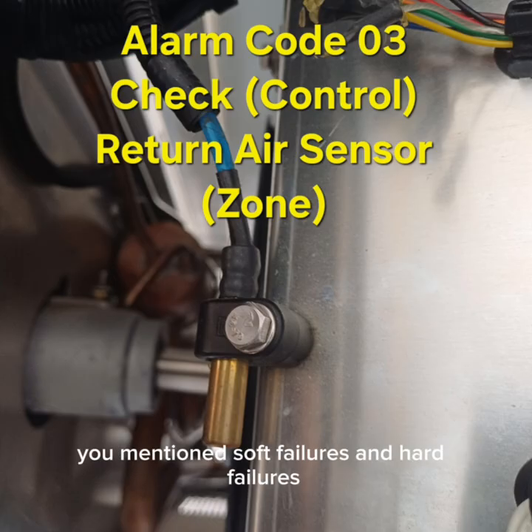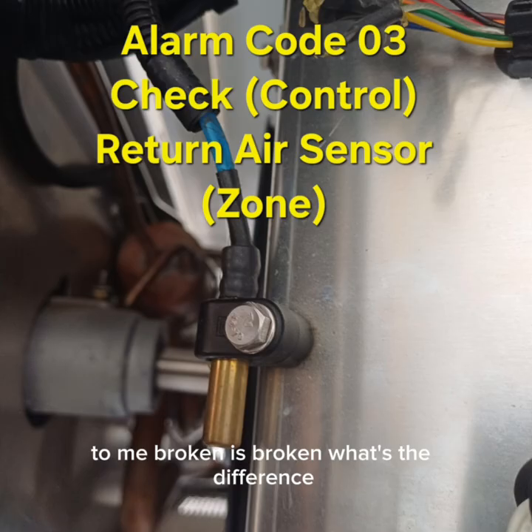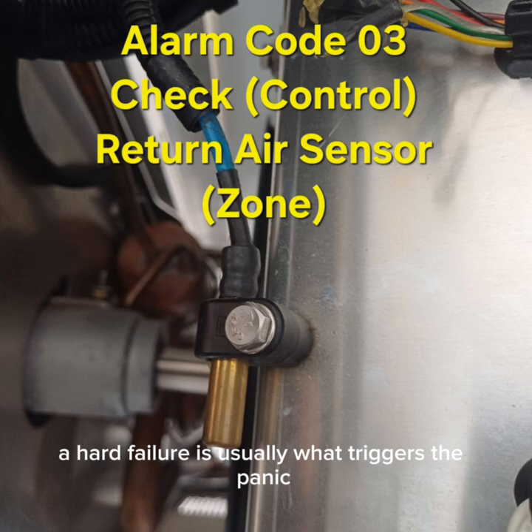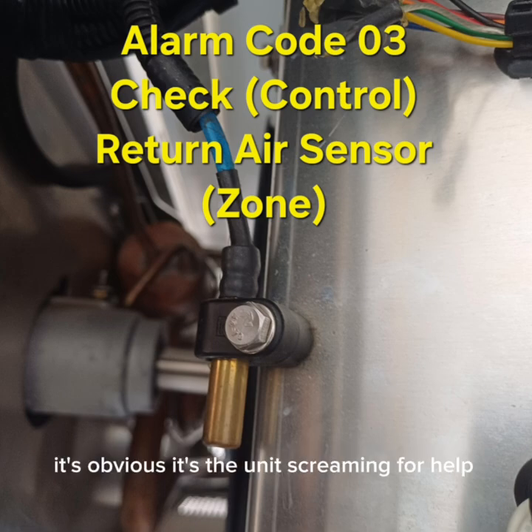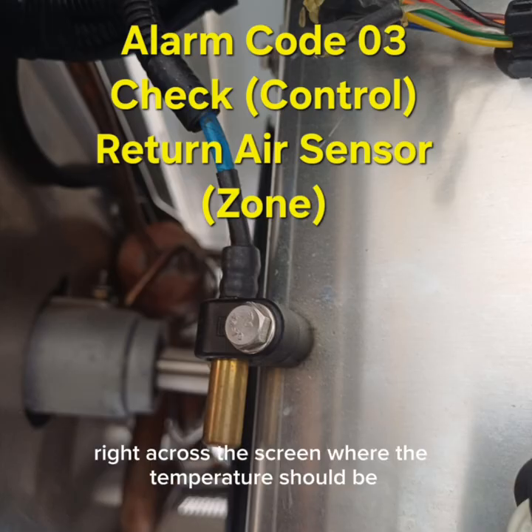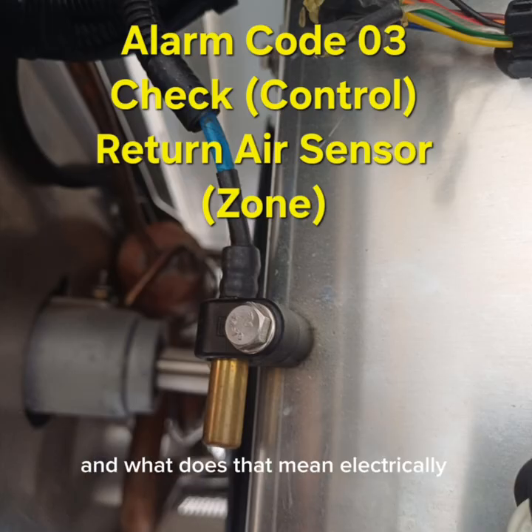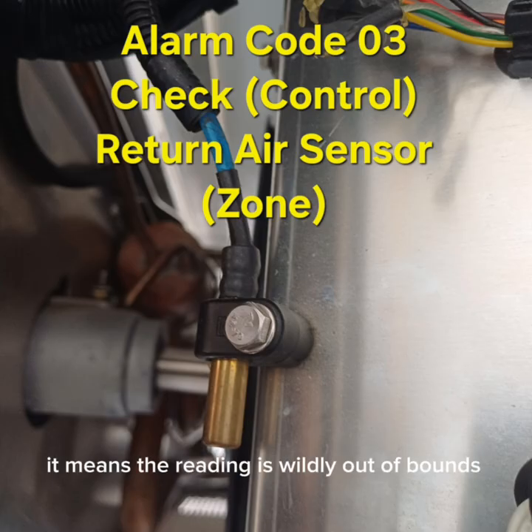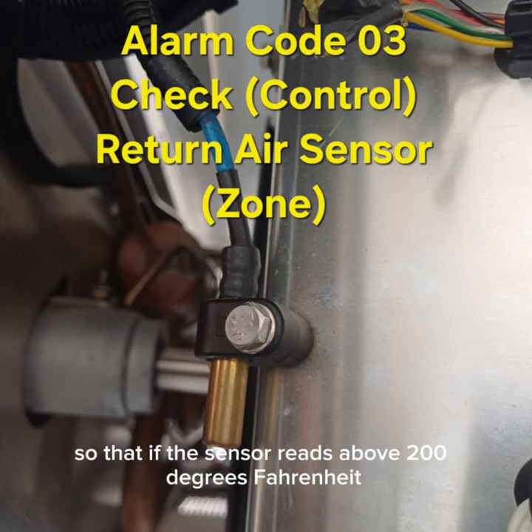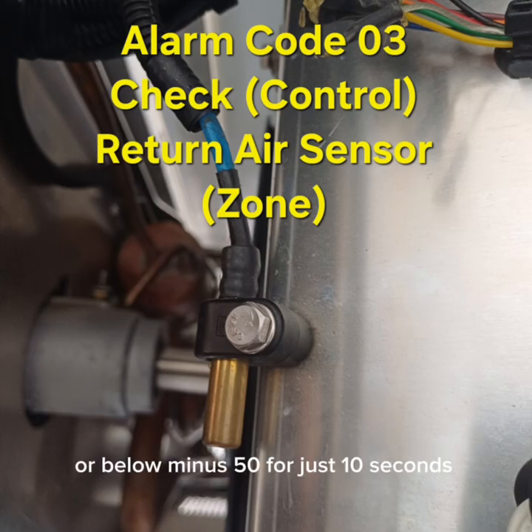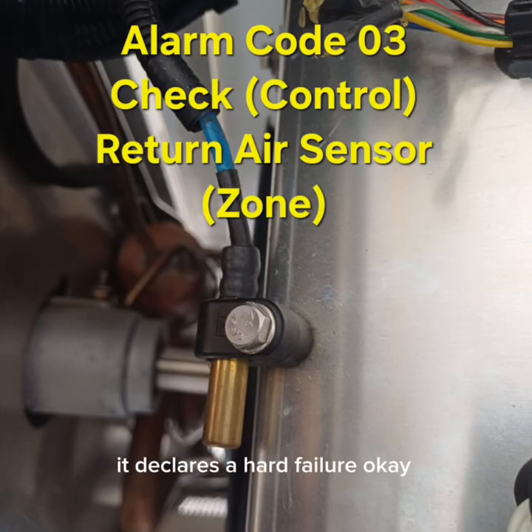You mentioned soft failures and hard failures. To me, broken is broken. What's the difference? This is where diagnostics get really interesting. A hard failure is usually what triggers the panic. It's obvious. It's the unit screaming for help. And what does that look like on the display? You'll see dashes, just 3 dashes right across the screen where the temperature should be. And what does that mean electrically? It means the reading is wildly out of bounds. The logic is programmed so that if the sensor reads above 200 degrees Fahrenheit or below -50 for just 10 seconds, it declares a hard failure.